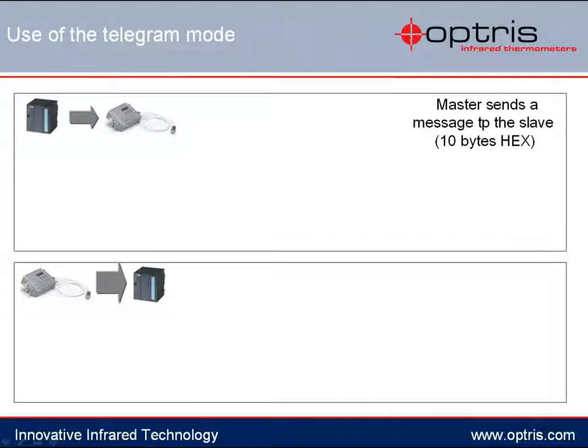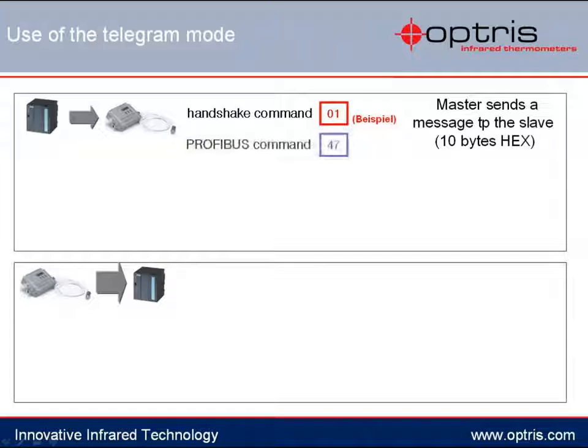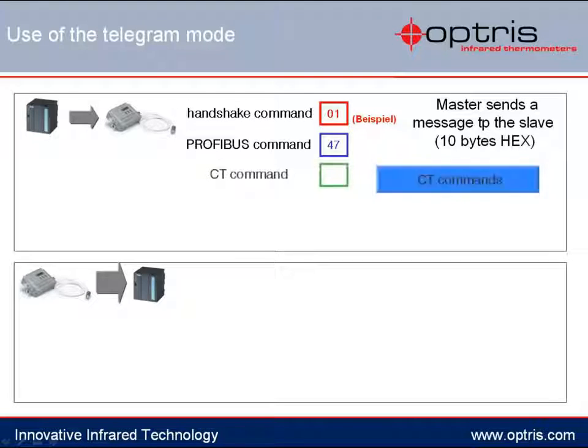The first byte consists of a handshake command. This command needs to include a different address after each completed sending and receiving process. The second byte is the PROFIBUS command 47, which informs the temperature sensor that a following command will be sent. The third byte includes the actual command, specifying which setting of the sensor will be changed or which information will be requested from the sensor.